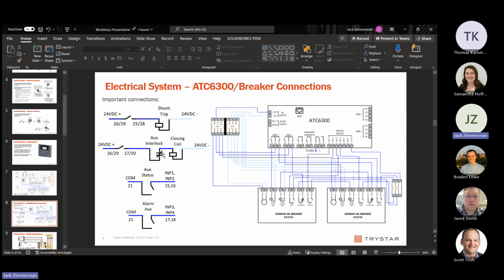So this is physically not letting the signal get to the other breaker closing coil until it goes through an interlock that says, I'm open, you're free to go. So it's optional because we already have a mechanical means of doing that, but I just added it in for extra safety and redundancy. So yeah, that's that connection.